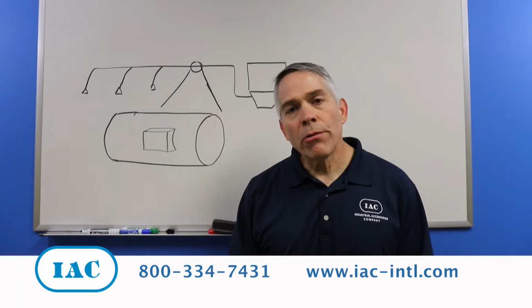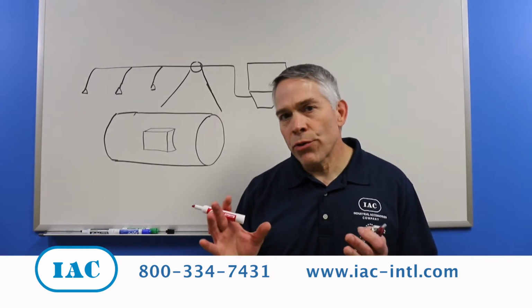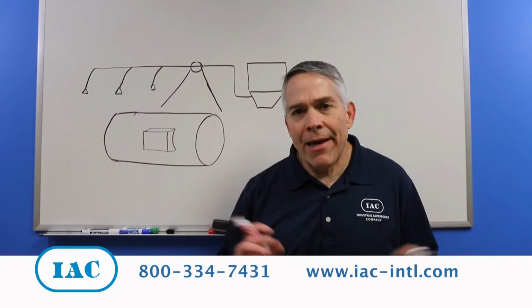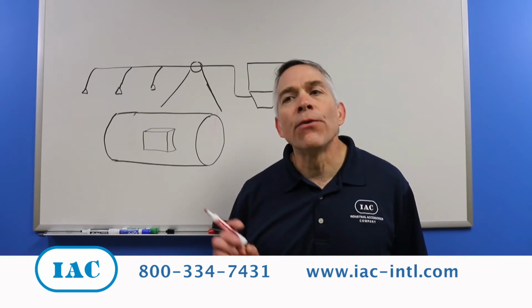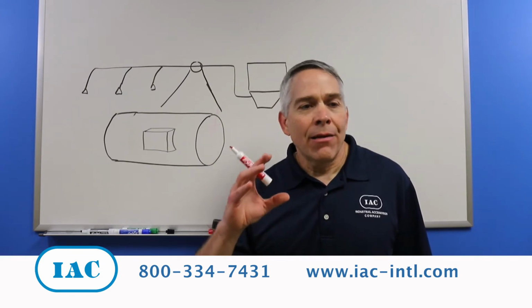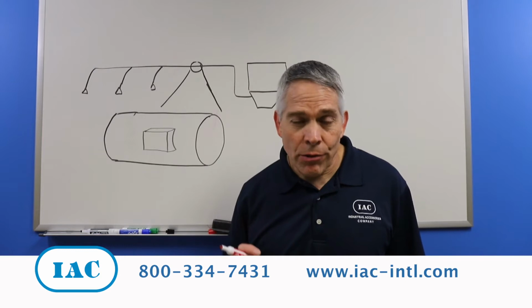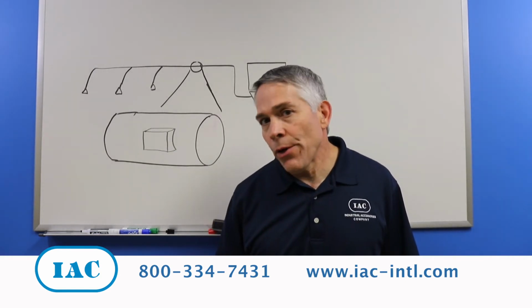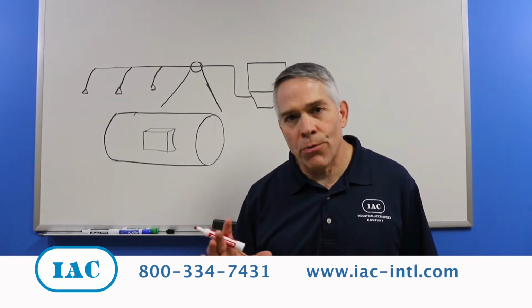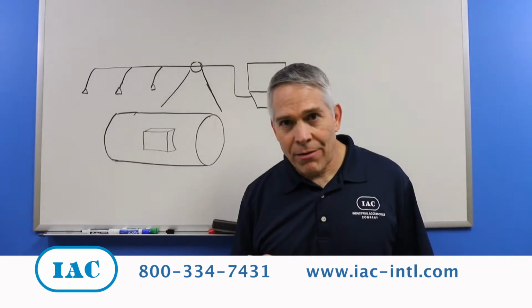This month we want to cover inspection doors and ductwork. Now, why would we need that? Generally, you wouldn't need it if ductwork was designed per global recommendations. One recommendation is that we don't want to run horizontal ductwork for long lengths, obviously.